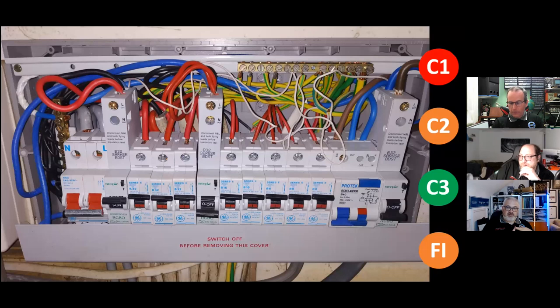Again, workmanship. The white fly leads, I'd be cutting them back, crimping them and putting them in their relevant terminals. Strain. Look at the strain on the main tails on the left. Bending radius of those conductors. Bending radius of the conductors on the tall RCBOs, access and maintenance of the neutral bar is difficult. It's just really poor workmanship.